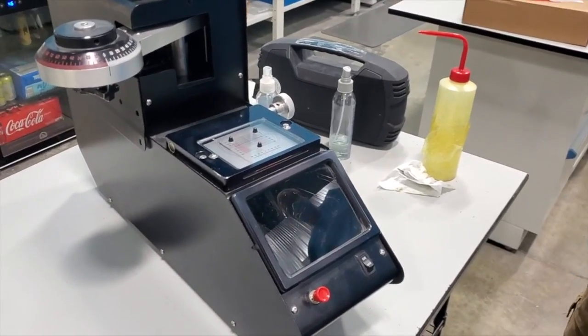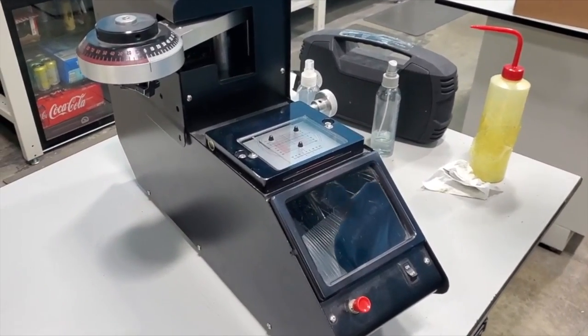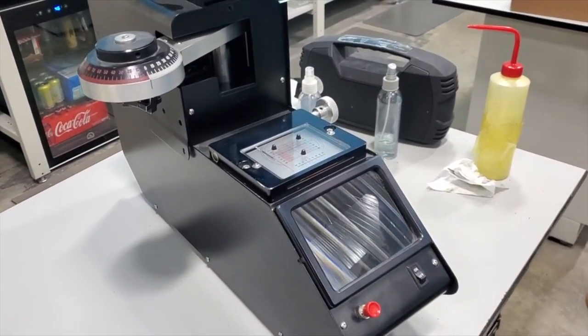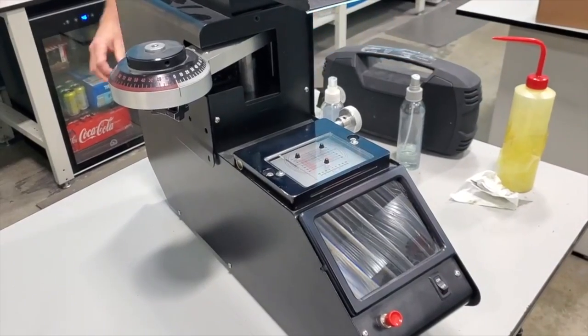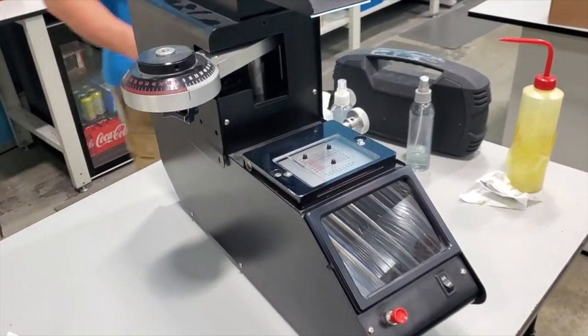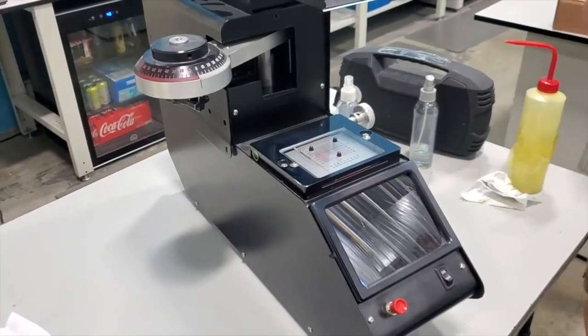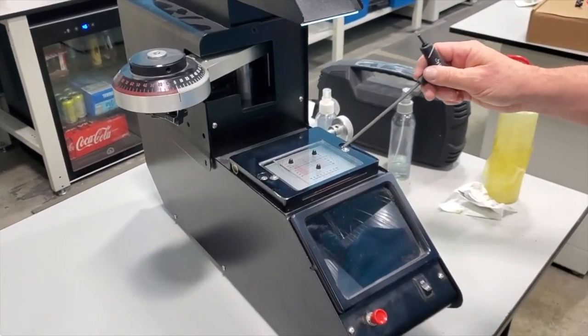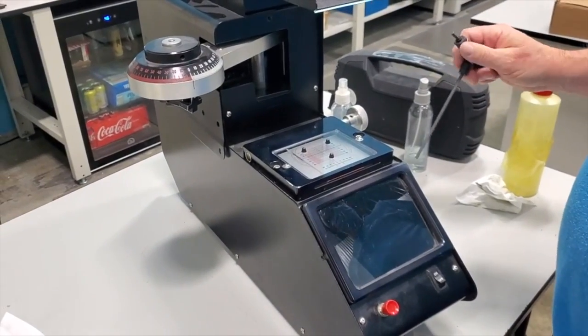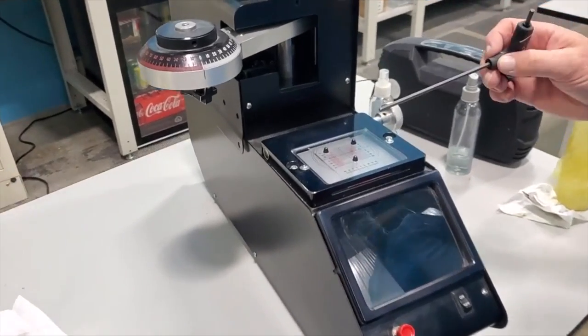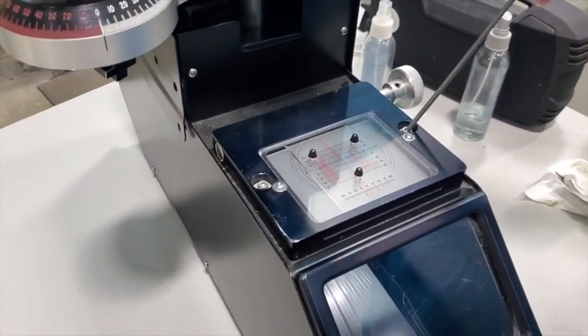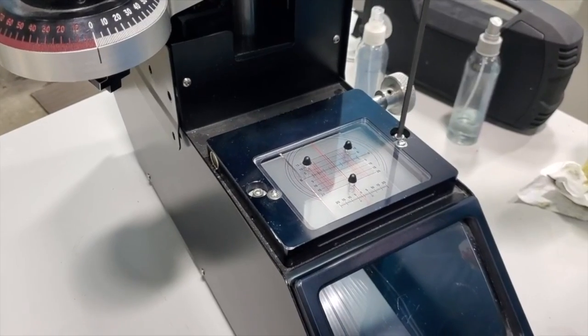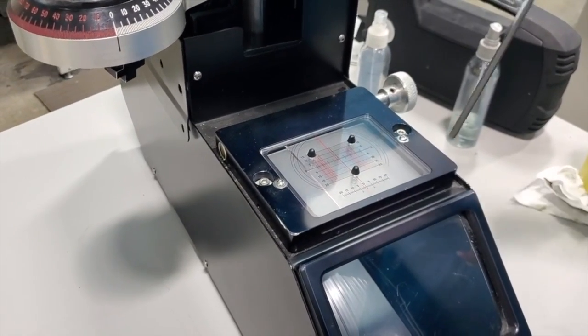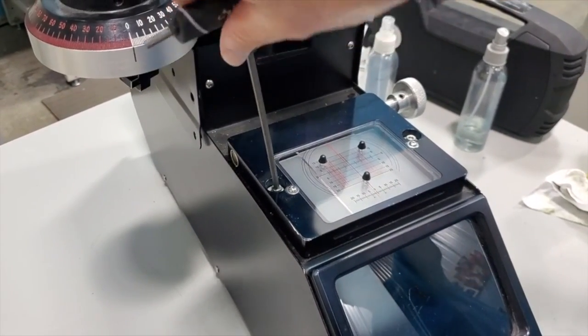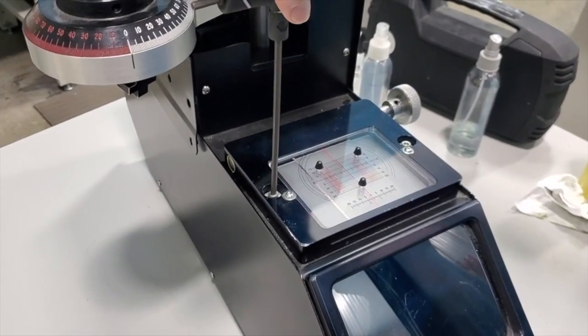Alright, so we went ahead and we verified the axis and centering alignment. Everything looked good for us. Now if for some reason that didn't look correct, what you're going to want to do is manually adjust this. So in order to do so, you're going to use an Allen key, and you're going to loosen the 2 bolts that Mike's pointing to right now. So you got one there and one right there. You would go ahead and loosen those up.